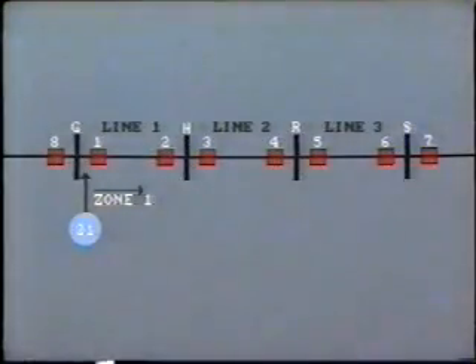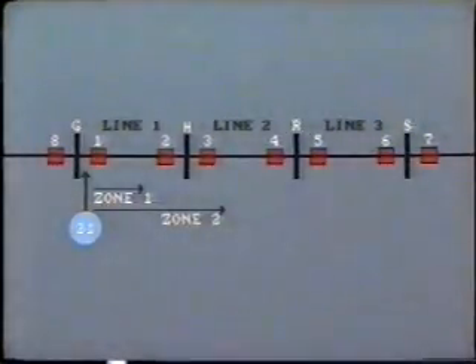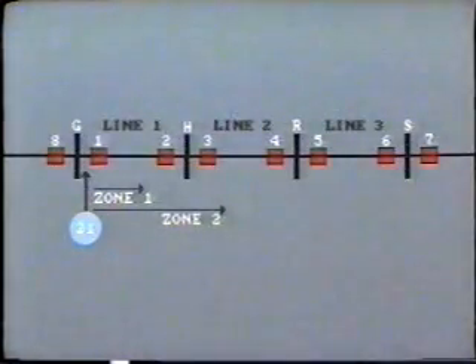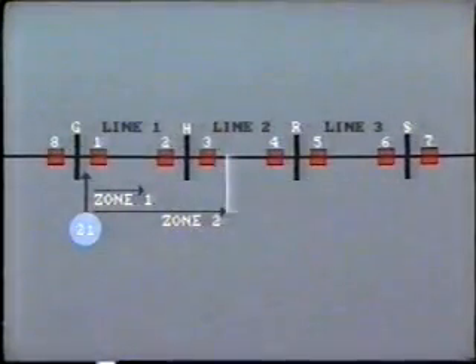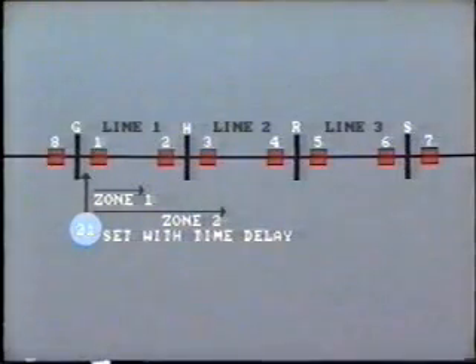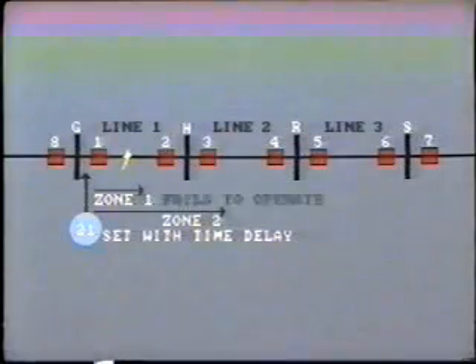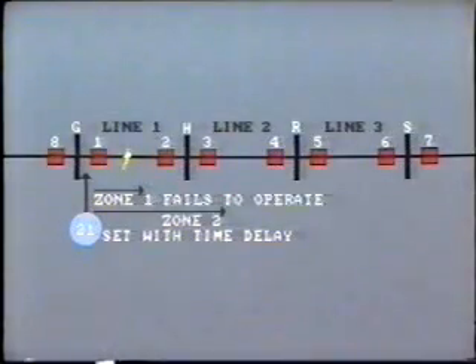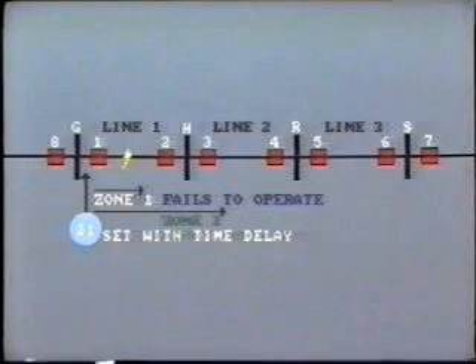The relay is also equipped with a second element, Zone 2, which is set to cover a longer distance. It will operate for a fault occurring along line 1 and into the first 20 or 30% of line 2. This is set with a time delay, so as to allow the Zone 1 element to operate first. However, for a fault within line 1, if the Zone 1 element fails to operate for any reason, then the Zone 2 element will pick up and operate.